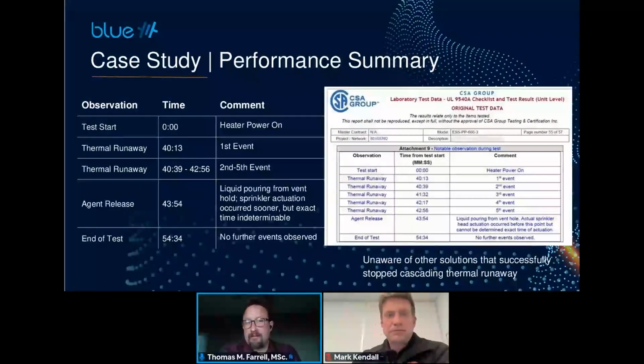And they provided in their report for that 9540A test some of these metrics. So we would call the start of the test; thermal runaway started at about 40 minutes, and that was with the first event of smoke being discharged from the module, which indicates that something is happening, and that's concurrent with the data with the temperatures going exponentially higher.